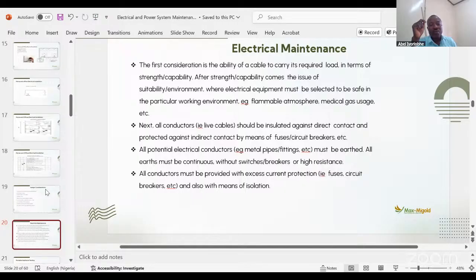All conductors must be provided with excess current protection - that is fuse, circuit breaker, etc. - and also with means of isolation. Every circuit must have means of isolation: the switch gear, the control switch, the changeover. So it is sectionalized, and you have to have all these things in place.